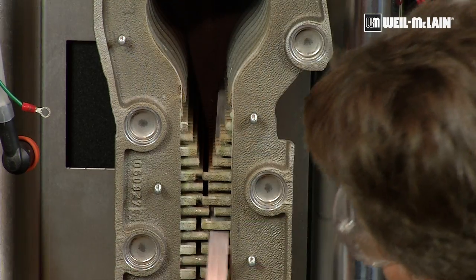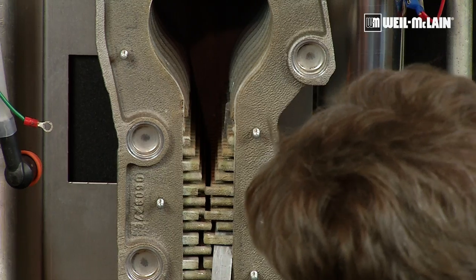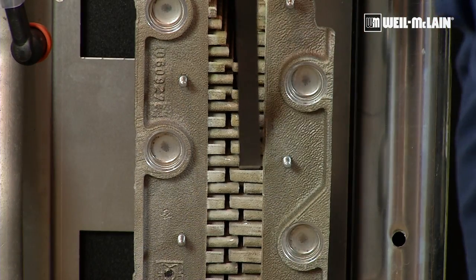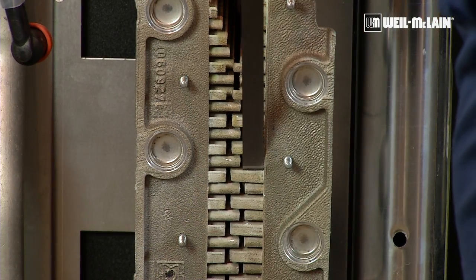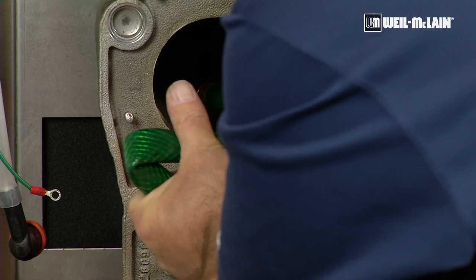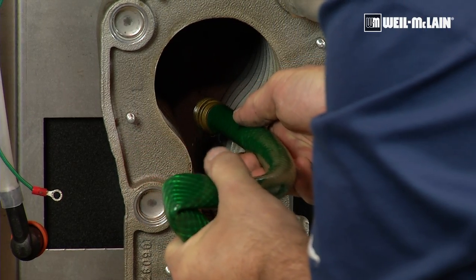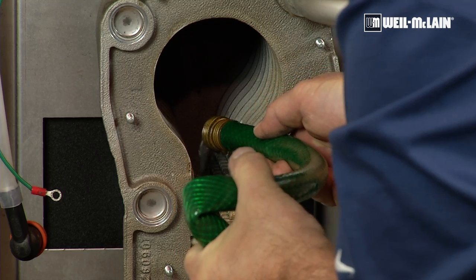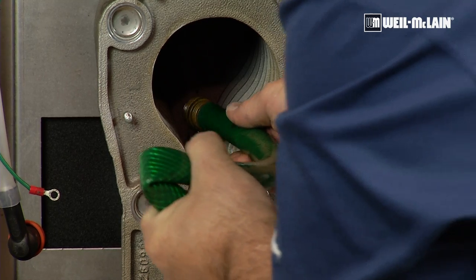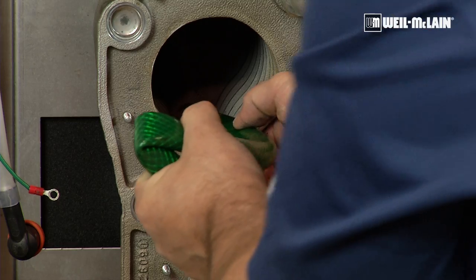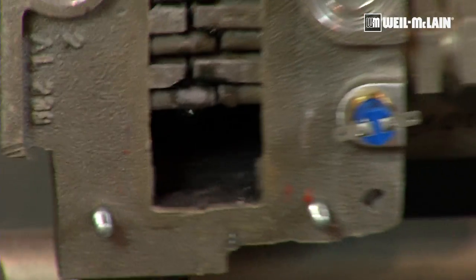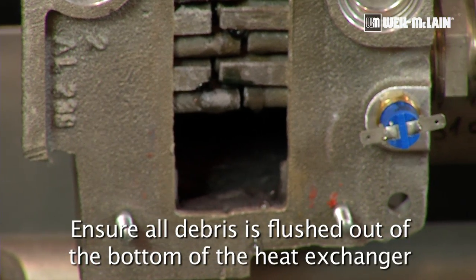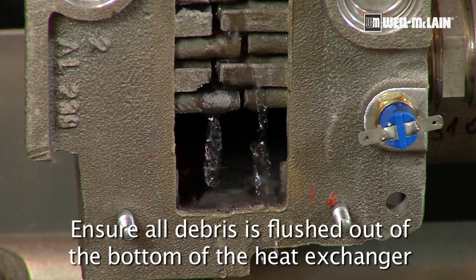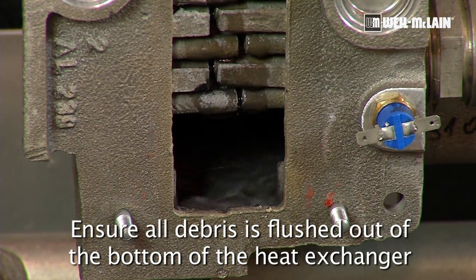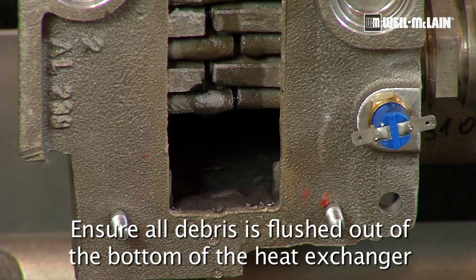So we want to make a pass on a 45-degree angle, both from the bottom up and from the top down. So the last step in the cleaning process is to rinse the debris down. And we don't need a fire hose here, right? But we want a good flow of fluid and to see it in the bottom of the heat exchanger.